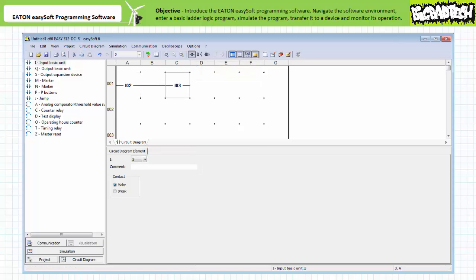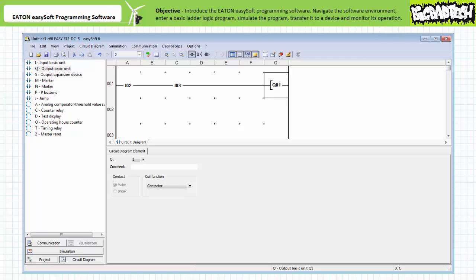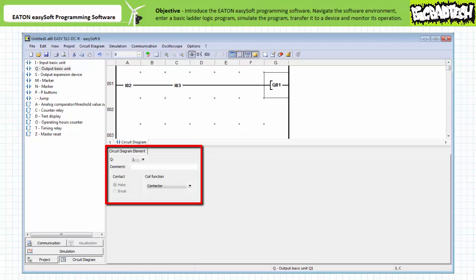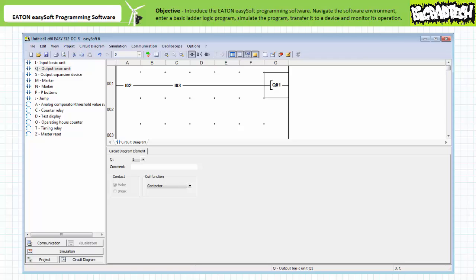If we change the operand number of the make instruction in rung 1, column A to I2, and drag another make instruction examining I3 into rung 1, column C, the software is smart enough to realize we want them wired together and inserts a wire in column B. If we place output Q1 in rung 1, column G, the programming software again does the wiring for us. Note the circuit diagram element tab allows a user to select the coil number, enter comments for later referencing or troubleshooting purposes, and select the coil function. If you mess up the wiring or if the programming software assumes an incorrect connection, you can always erase the wire using the eraser button and redraw it using the draw connections button. Our program is a series connection of two make instructions examining inputs I2 and I3, yielding a coil output Q1. One can save this program for later editing and reuse — I'm going to call it demo program.